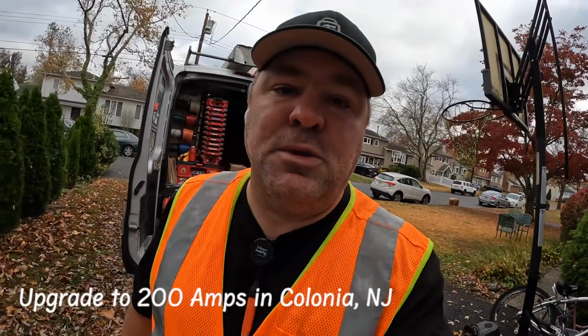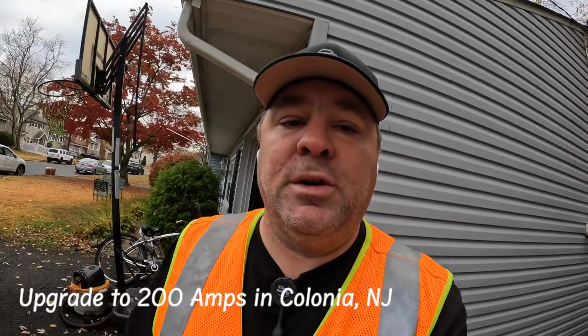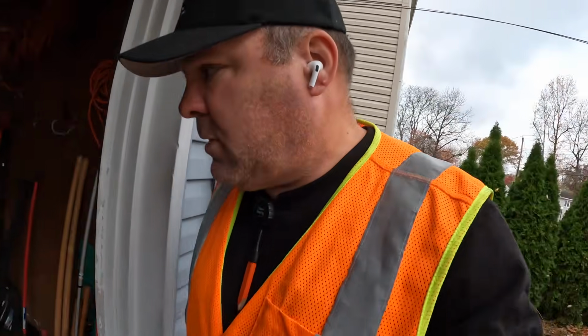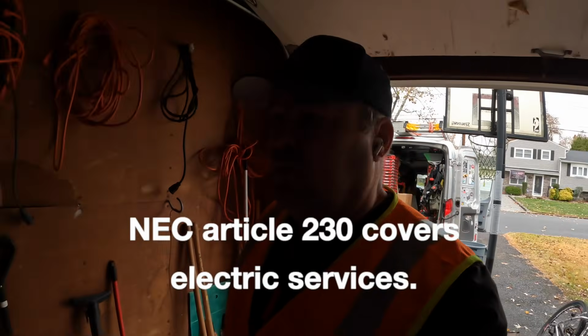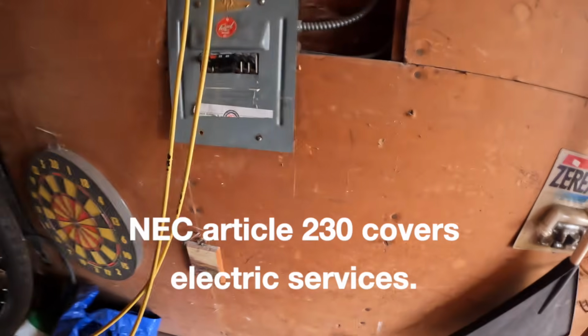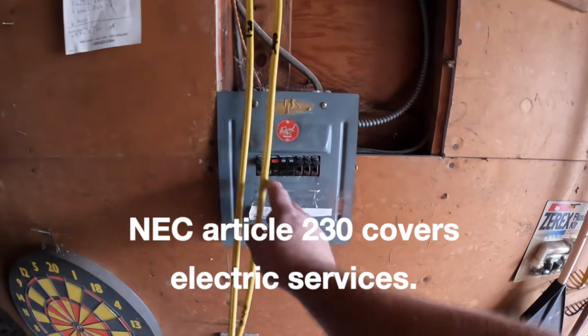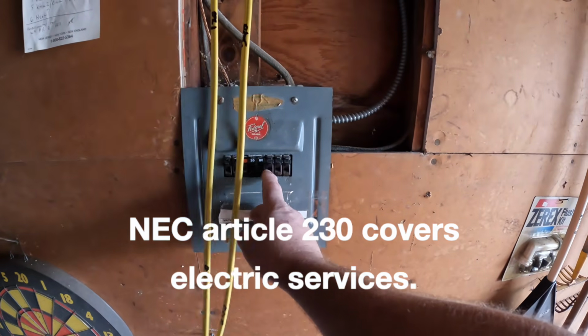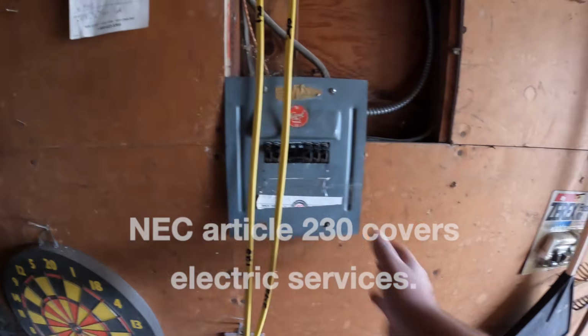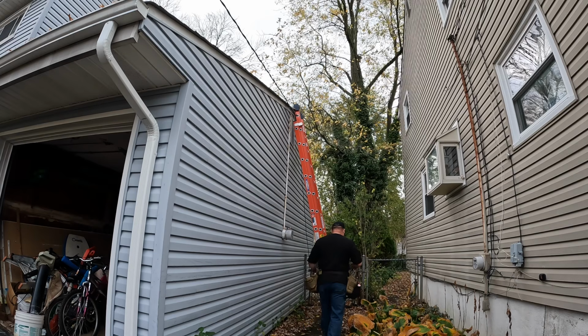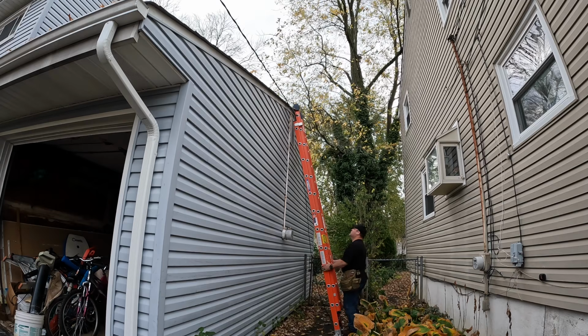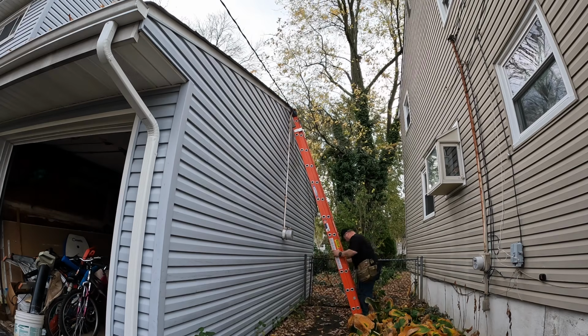We've been plenty busy, but today we're doing a 200 amp service upgrade here in Colonia, New Jersey. You can see the service behind me. This is an old 100 amp service. On the inside, I don't have my light set up. I literally just pulled up. We have this Federal Pacific panel, and it's got 1, 2, 3, 4, 5, 6, 7, 8 circuits, no main breaker. I always like when I can come in and replace an old Federal Pacific electric panel.